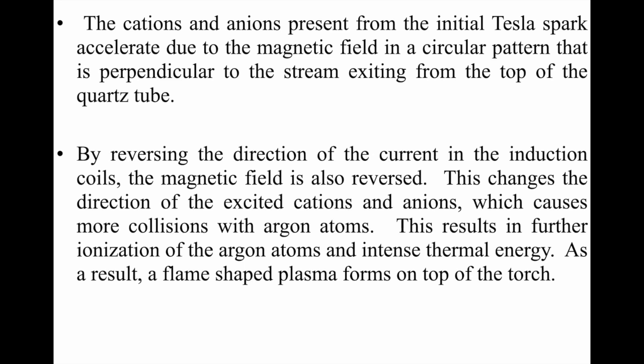The cations and anions present from the initial Tesla spark accelerate due to the magnetic field in a circular path perpendicular to the stream exiting from the top of the quartz tube. By reversing the direction of the current in the induction coil, the magnetic field is also reversed. This changes the direction of the excited cations and anions, causing more collisions with the argon atoms, resulting in further ionization of argon atoms and intense thermal energy. As a result, a flame-shaped plasma forms on top of the torch.